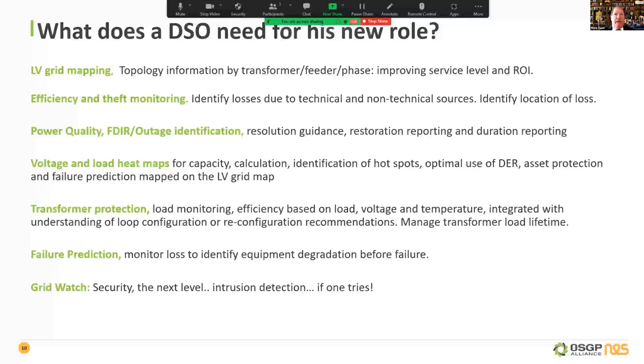Voltage and load heat maps, so that you don't blind guess the capacity requested in feeders and transformers, but basically get actual information, identify the hotspots, the heat maps, where significant draw of current is taking place, maybe because of those electric vehicles which spread around. But the same with voltages - if multiple people start feeding into the grid, you will see the voltage going up to a level where you cannot manage it anymore.